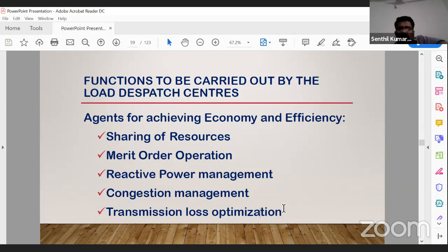Why does transmission loss optimization come in? Generation happens in one place and is utilized in another area. For example, from Orissa to Chennai or from Orissa to Kolar in Karnataka, power transmitted through HVDC lines has very meager loss. In case of AC transmission lines, there is a minimum loss of about 2% to 3%. How we calculate this loss, how we share it among every state, and how we optimize that loss - these things are also managed by the system operator.